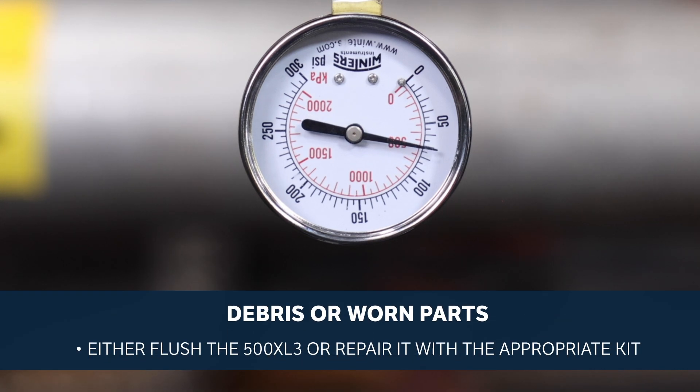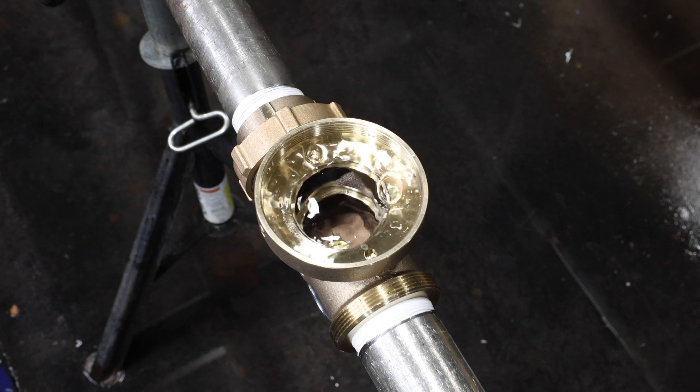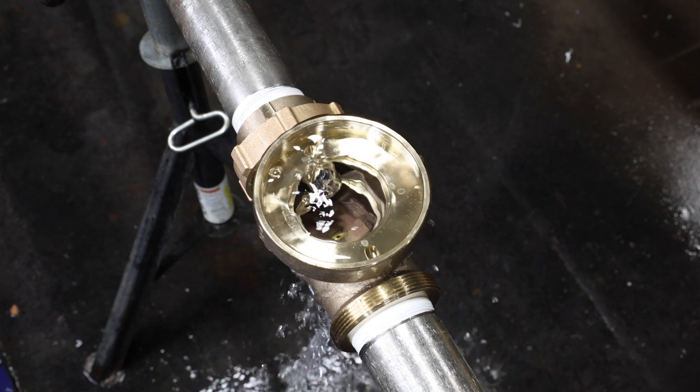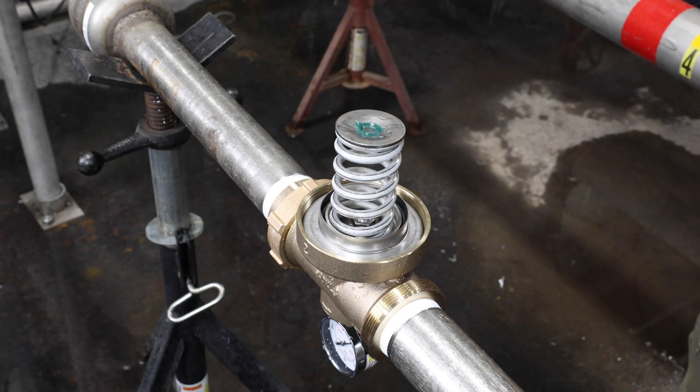Pressure will be relieved the next time a fixture is opened downstream of the 500 XL3. If pressure frequently builds up above the outlet pressure, then debris build up or worn parts may be the problem. To correct this, either flush the 500 XL3 or repair it with the appropriate Zurn repair kit. We will cover instructions for both later in this video.